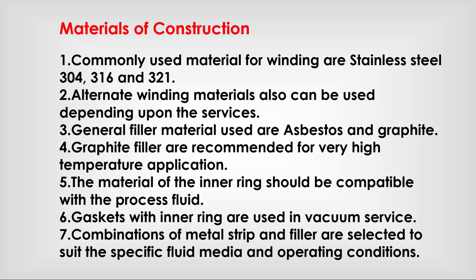General filler materials used are asbestos and graphite; graphite fillers are recommended for very high temperature applications. The material of the inner ring should be compatible with the process fluid. Gaskets with an inner ring are used in vacuum service. The combination of metal strip and filler is selected to suit the specific fluid media and operating conditions.